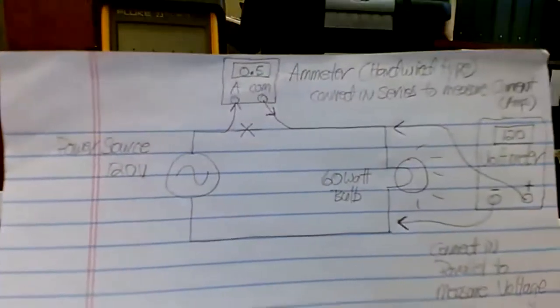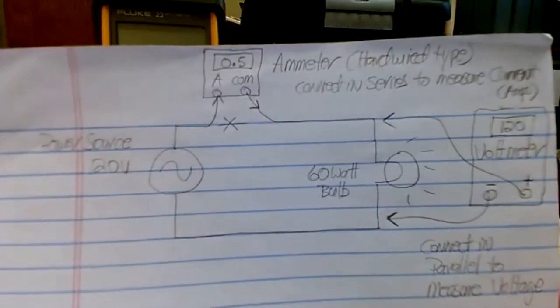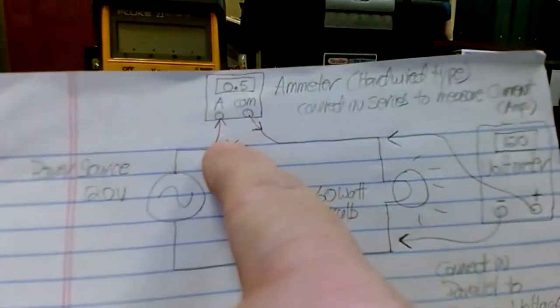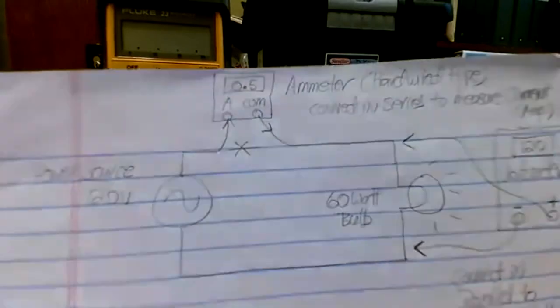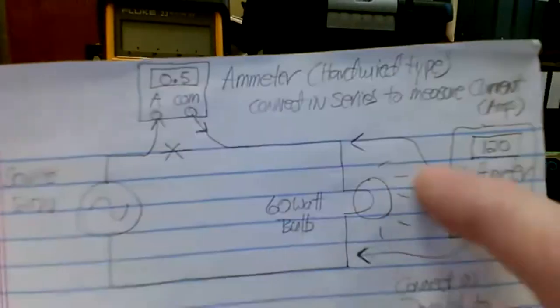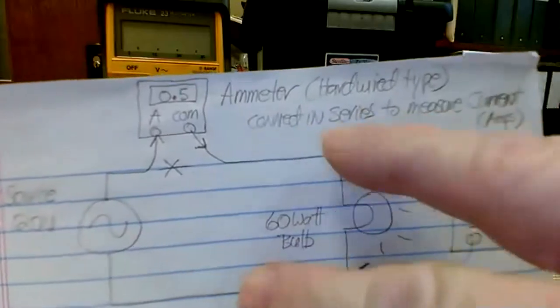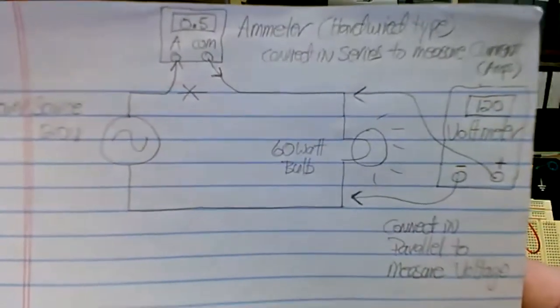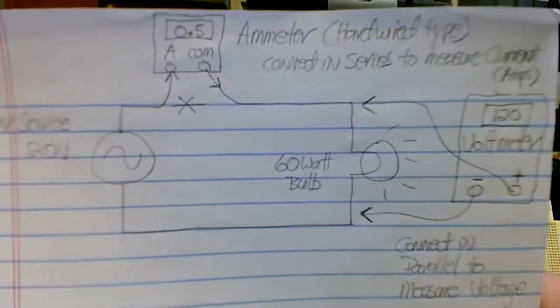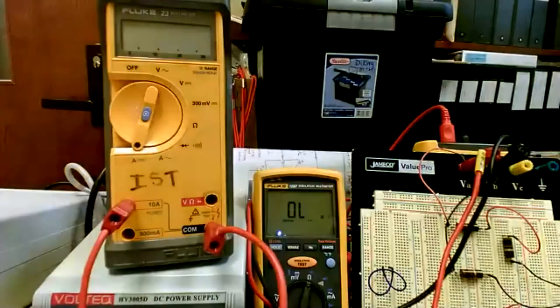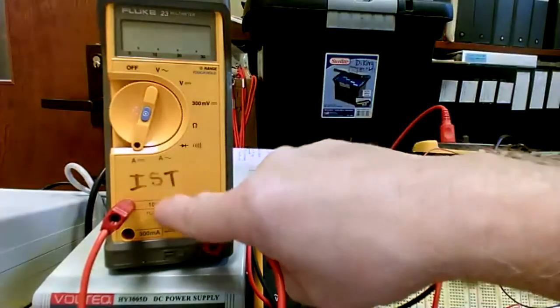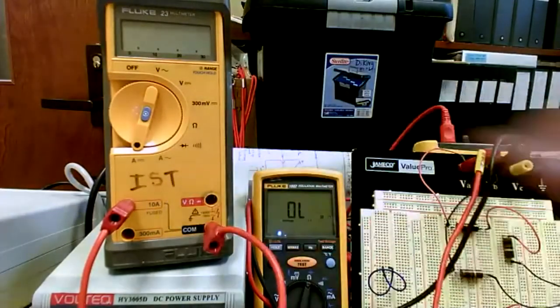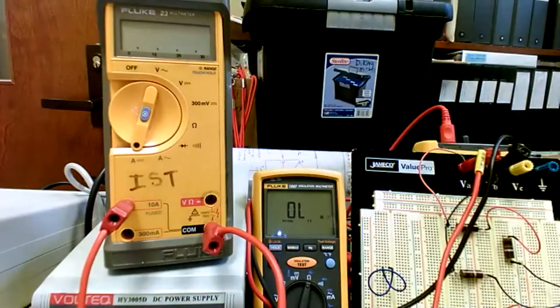So for checking current with a traditional ammeter, it has to be in series. But to check volts, you place the voltmeter in parallel across the load to get a reading. Everybody understand that? Yes, sir. Okay. But again, you do have to have a meter that has inline ammeter jacks to be able to do that. You pay a little more to get them, but it is necessary in some cases to have that.